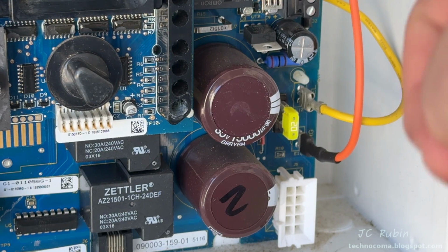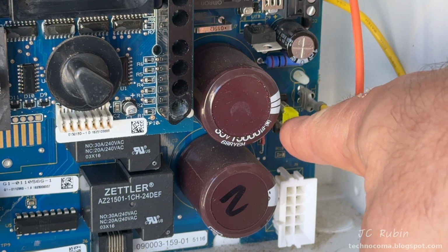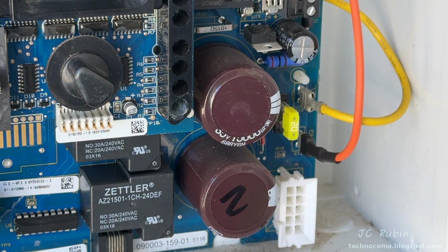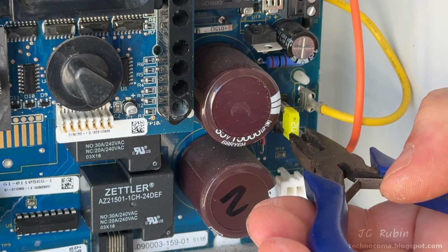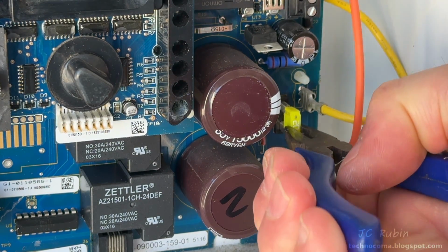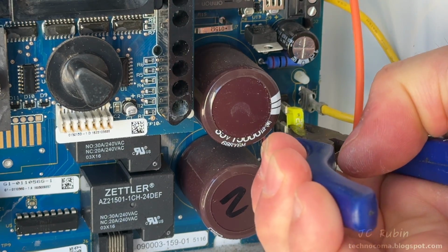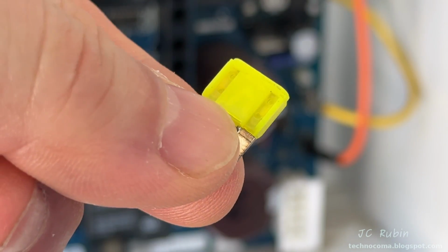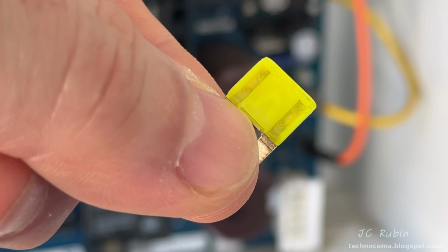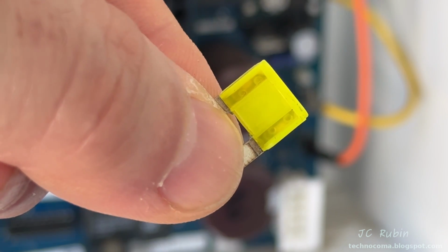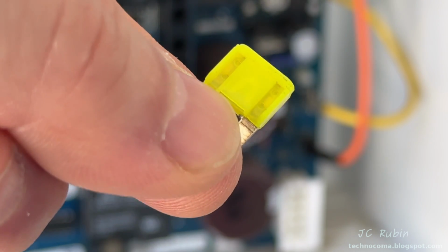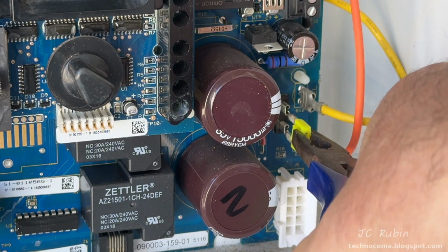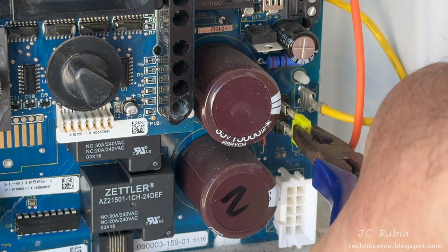I always like to point out, if you're getting no indication whatsoever, check this fuse right here, this 20 amp fuse. We're going to pull it out with a pair of pliers. A gentle wiggle back and forth will get it loose from its seat. I can see from a visual indication that it's fine, though it doesn't show on camera. I would definitely recommend an ohm meter for continuity checks. This one is good. I'll seat it right back in with the pliers.